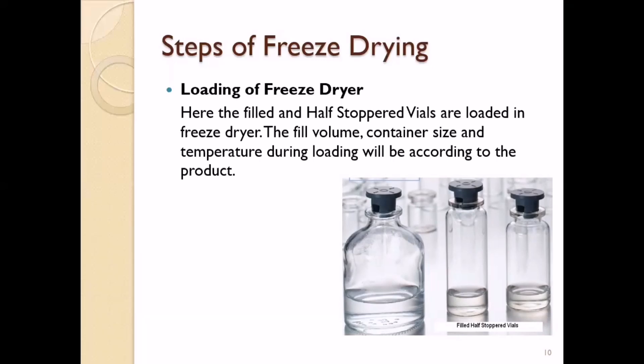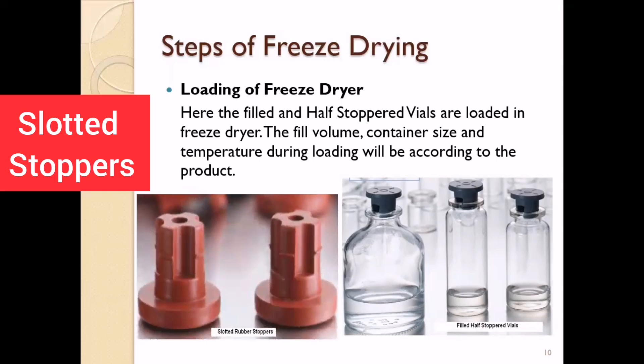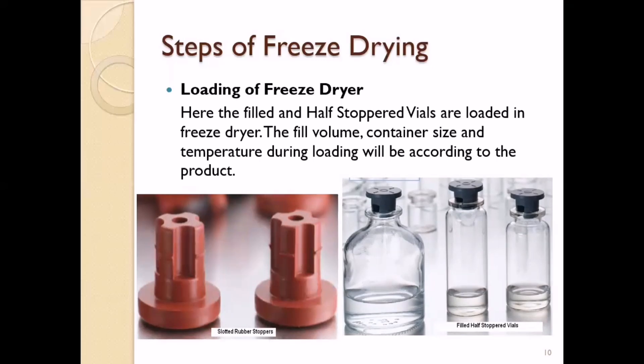These are specially designed stoppers called slotted rubber stoppers, which have a slot. When pressure is applied and the vial is loaded into the freeze-dryer, this slot keeps the stopper in the half-stoppered position and prevents it from completely sealing the vial.